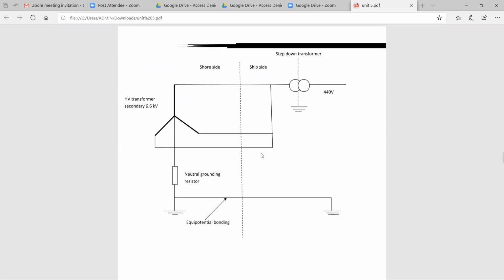Usually you have a shore section high voltage transformer. This high voltage transformer has a capacity of 6.6 kilovolt, and then you have a neutral ground resistor, and then equipotential bonding. The second section has a step down transformer with a rating of 440 volt. On the ship side you have a step down transformer. On the shore side you have a high voltage secondary 6.6 kV system. So this system can be operated from the shore side to the step down transformer side. The step down transformer is located on the ship side. On the shore side you have a high voltage transformer in the category of 6.6 kilovolt.